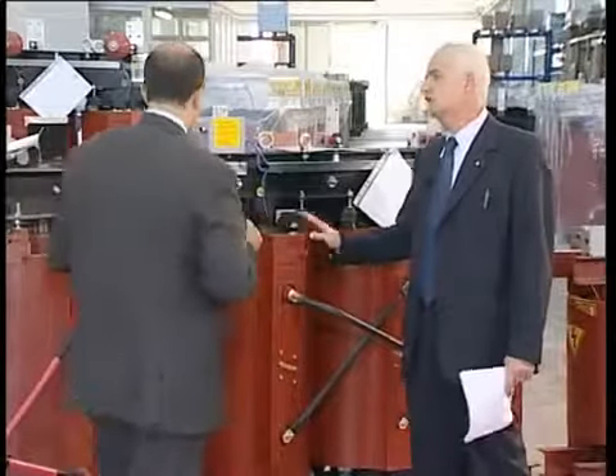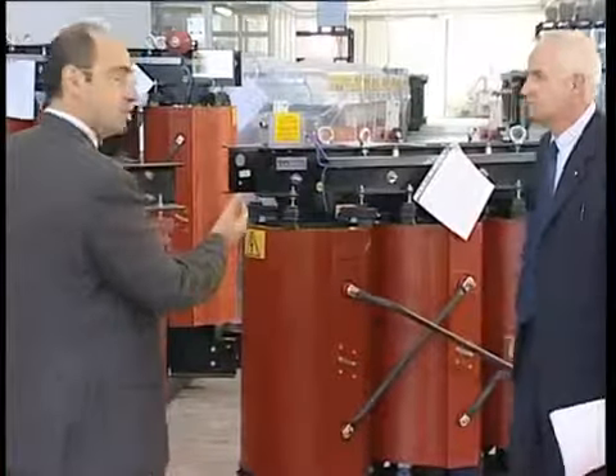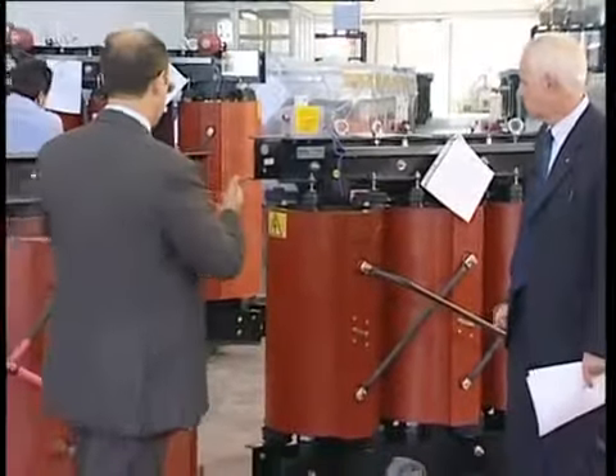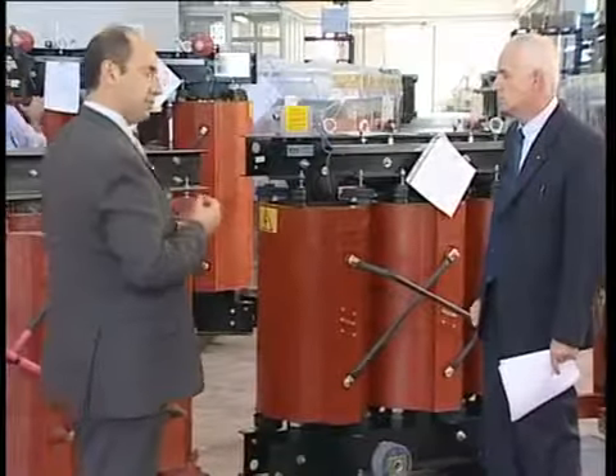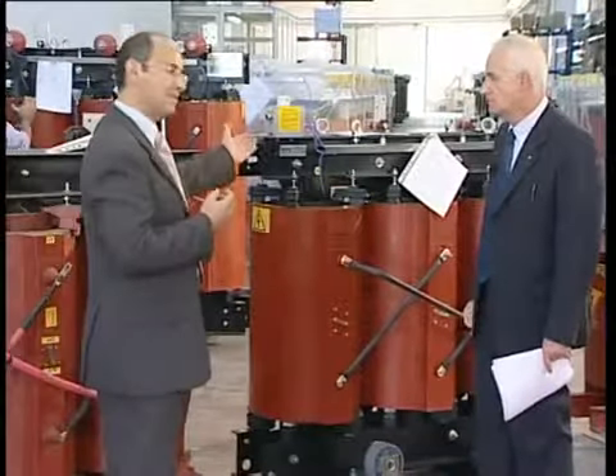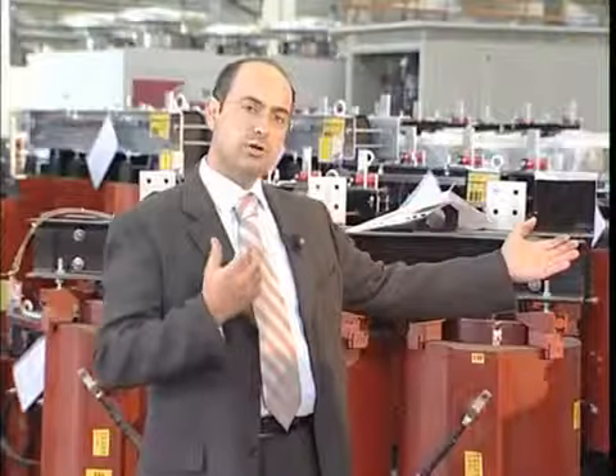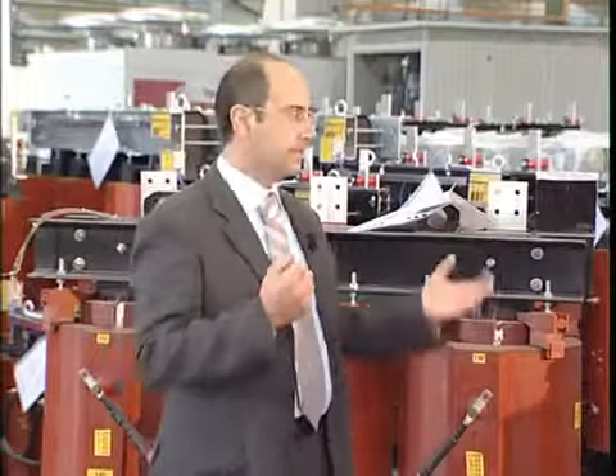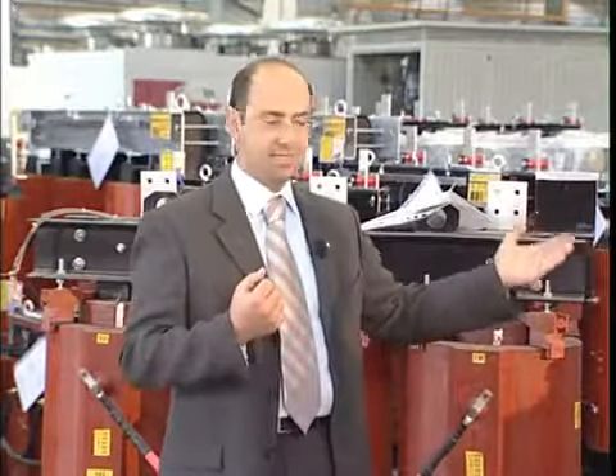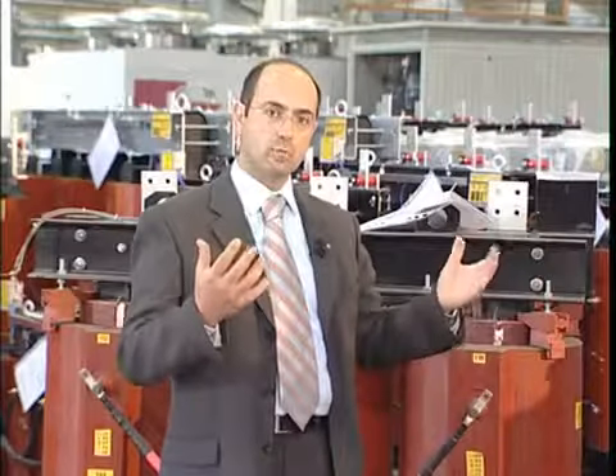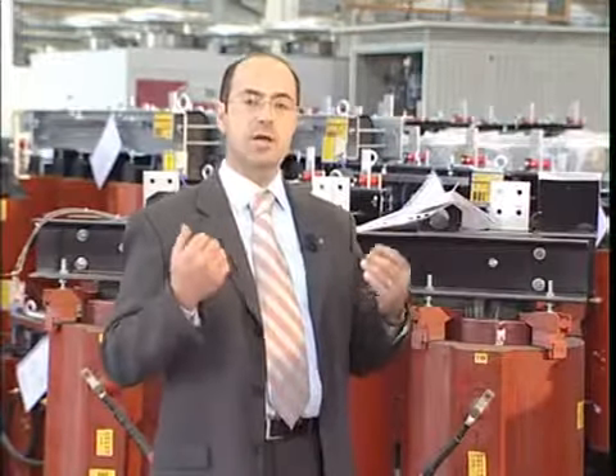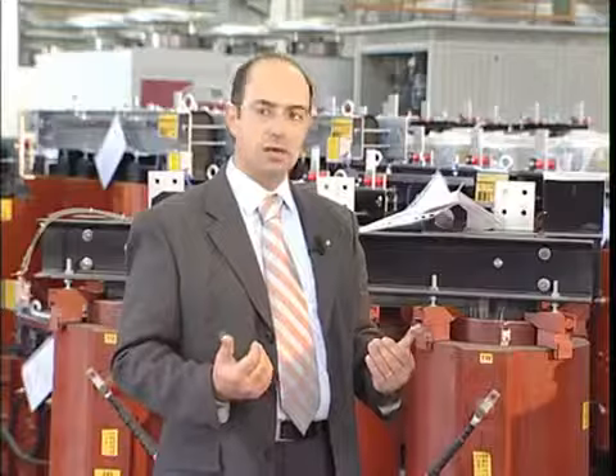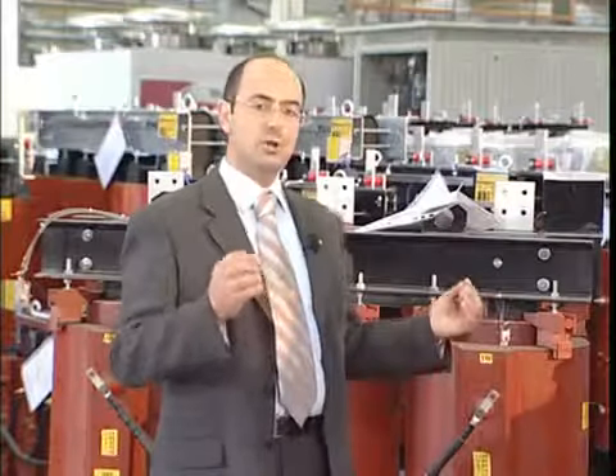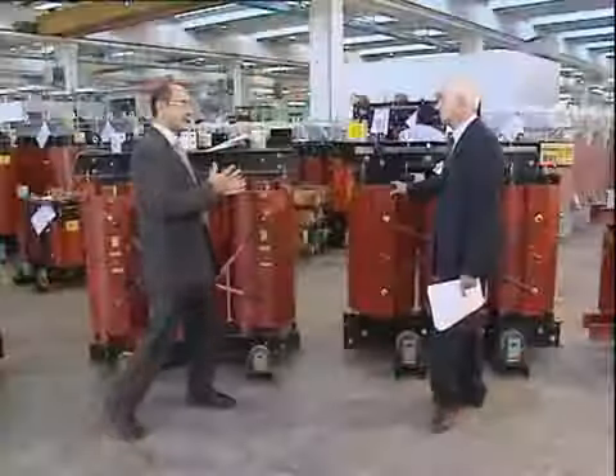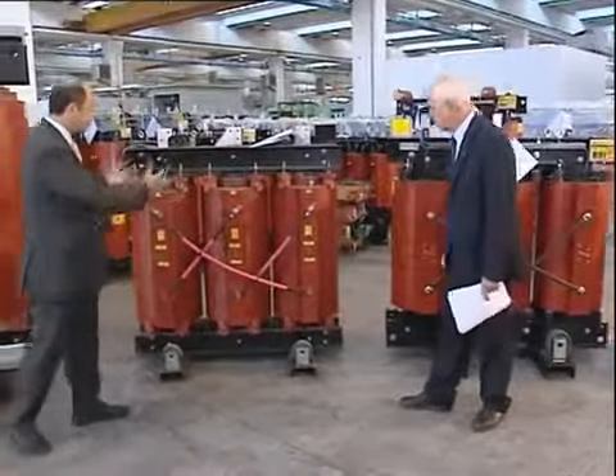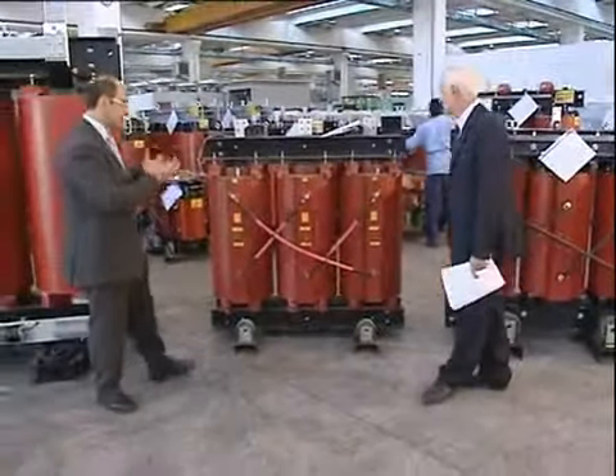There are differences. In equal-sized conditions, we could see that the insulation distances in our transformer are twice as large, just like the cooling surfaces in the low-voltage winding, which is the one exposed to the highest current. As a consequence, our equipment will undoubtedly have a far lower operating temperature and a much longer life, since the insulating materials undergo a considerably lower thermal stress compared to a not-so-high-quality transformer.